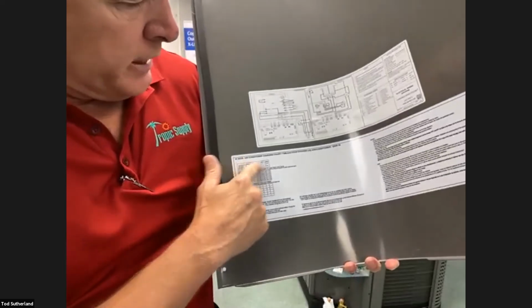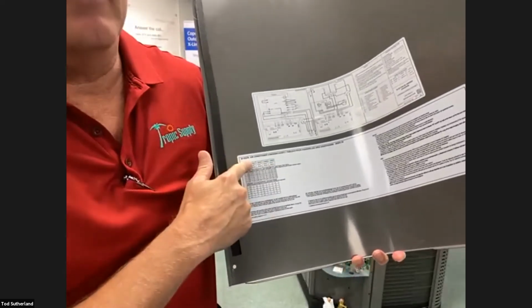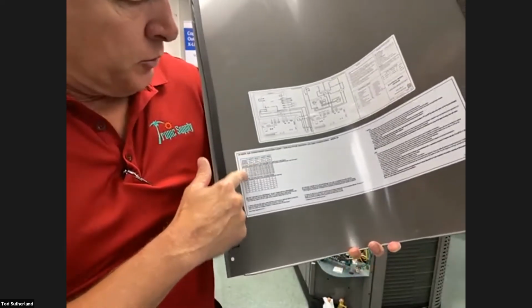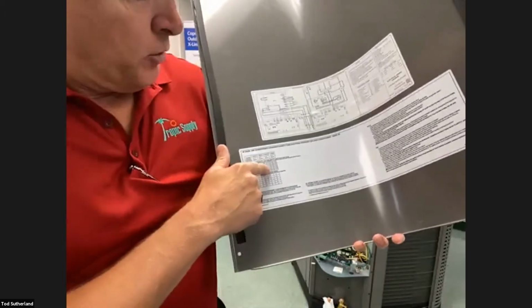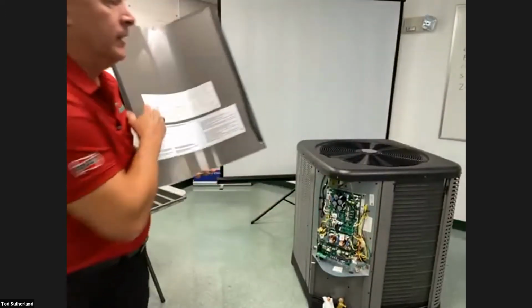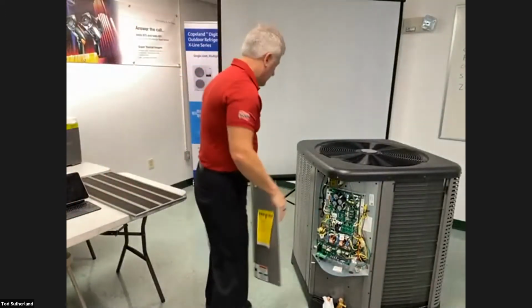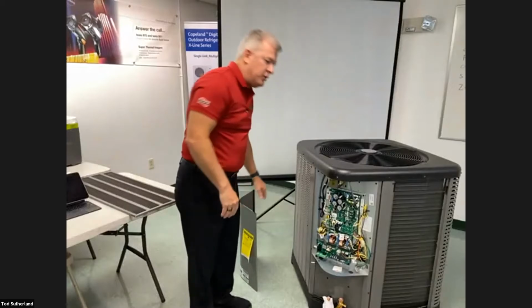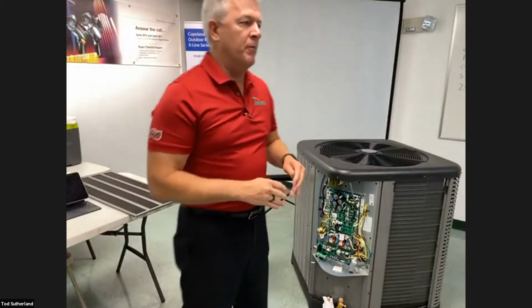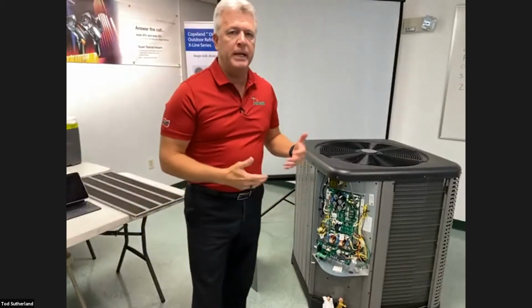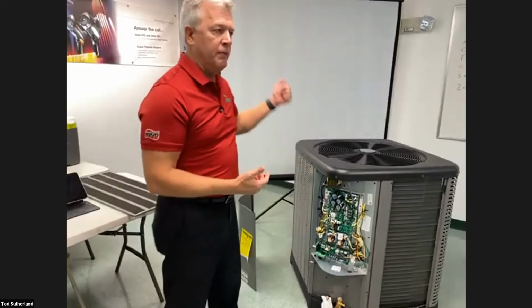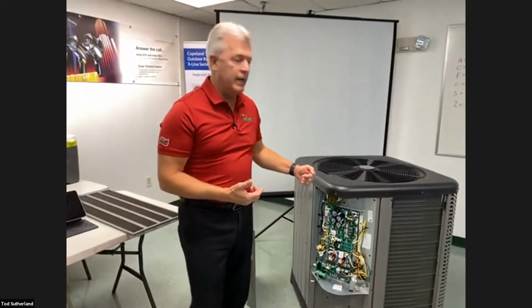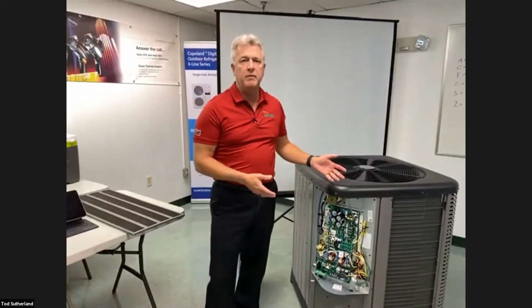It's going to show you what unit you have up here, what tonnage, and then it's going to show you what your outdoor ambient is, and you run across and it's going to give you what your high side and low side gauges should be reading. Okay, that's just to get you close. Then from there, you're going to want to adjust the charge based on subcooling, and as you drop down in that chart, it's going to tell you how many degrees of subcooling it's looking for.